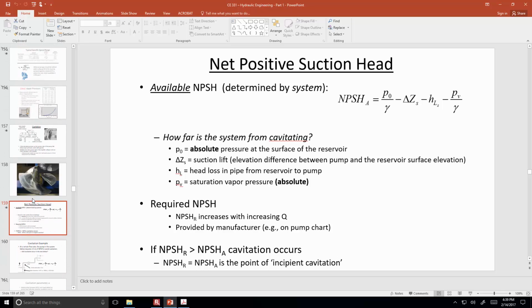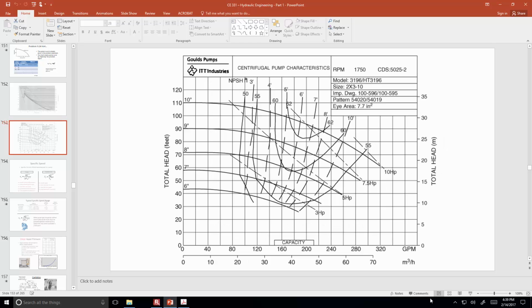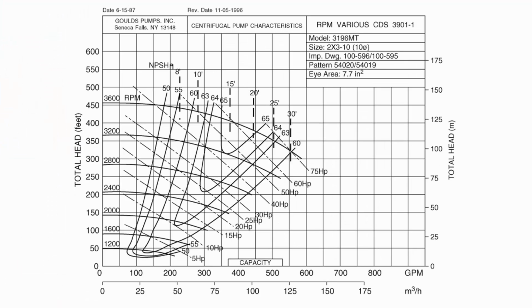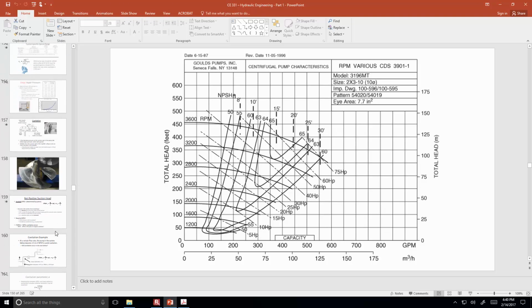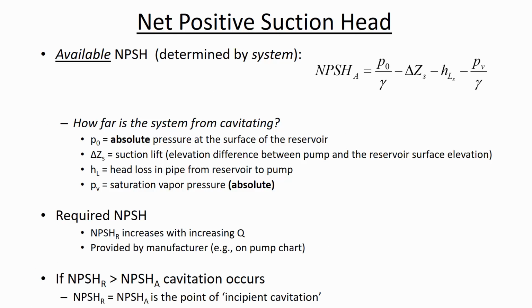And let's look at that figure that we saw just a moment ago here. That's not it. Okay, this one. So as the flow rate goes up, this is how much head is required by the pump to avoid cavitation. So at a low flow rate like 225 gallons per minute, it only needs 8 feet of head. So you're far away from cavitation. But as the flow rate increases, it's requiring more and more head. And so the required versus the available is what we're going to be comparing. And if the available is less than required, then cavitation will occur. And so here is the diagnosis criteria that you're going to need to be able to apply. If the required suction head is more than what's available, then there's cavitation. Now, if they're equal to each other, that is called the point of incipient cavitation, which means it's just about to cavitate.